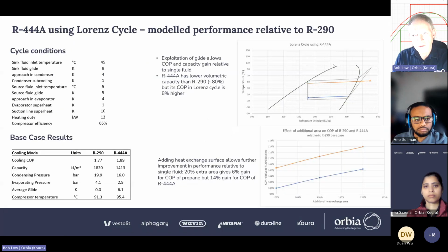So just another note on how it could be used in a Lorenz cycle. I can't share COP data yet, but I can share model data. So this is 444A compared to propane, at an AC-type point: 45°C inlet temperature to the condenser with an 8K glide, and 5°C on the cold side as the evaporator heat source, and the baseline is propane in this instance. I wanted to give it more of a challenge. Putting in YF would be too easy. It would look so much better.